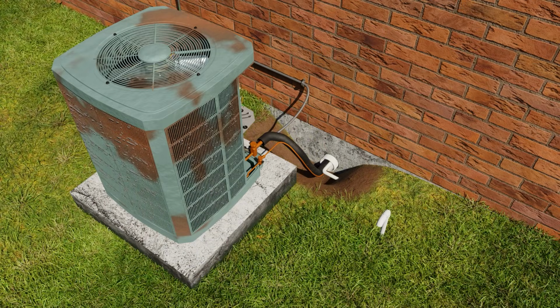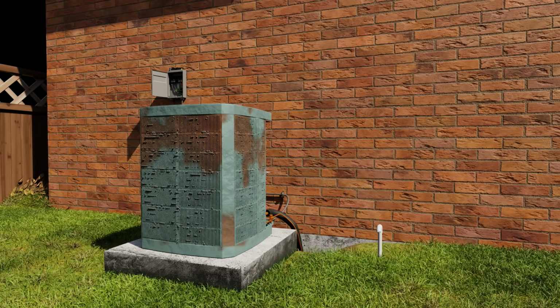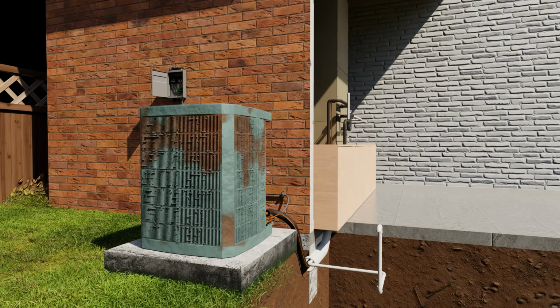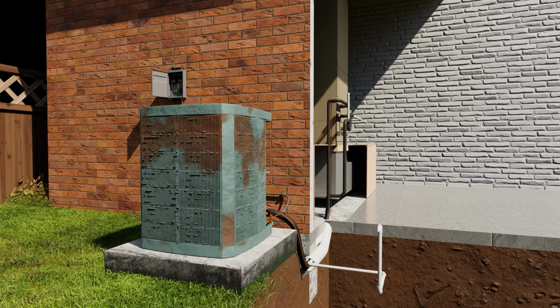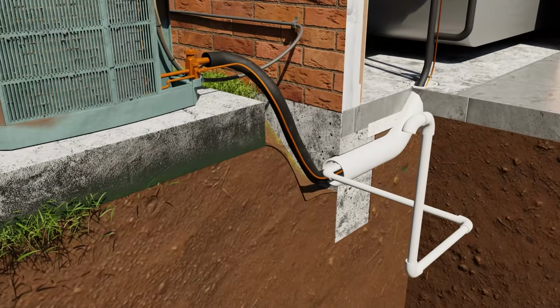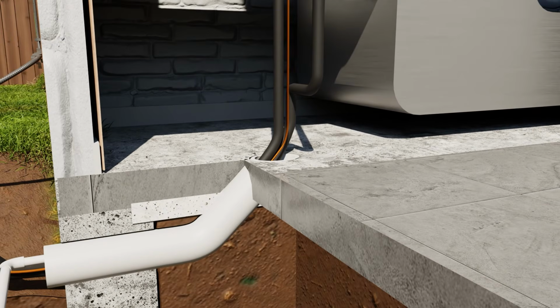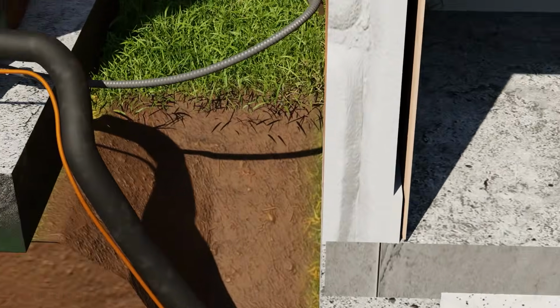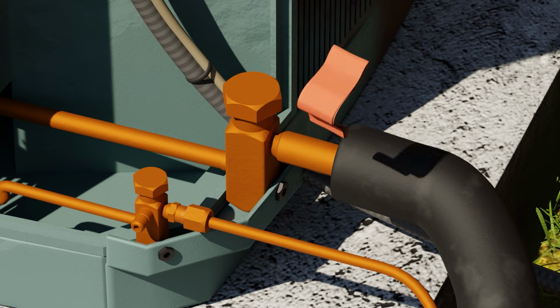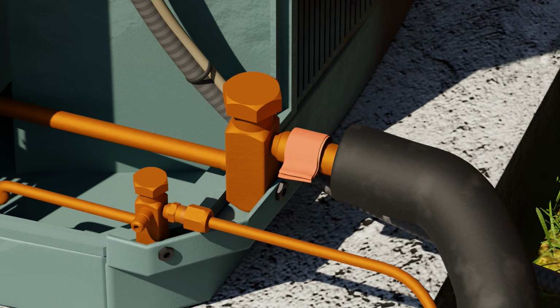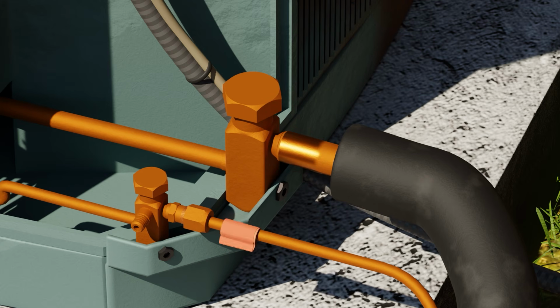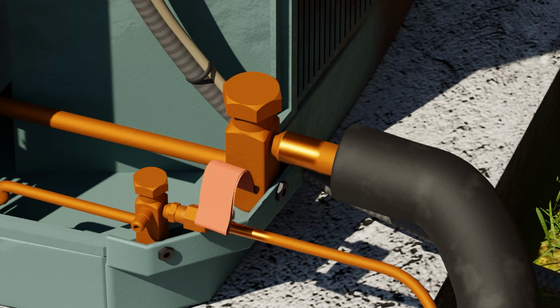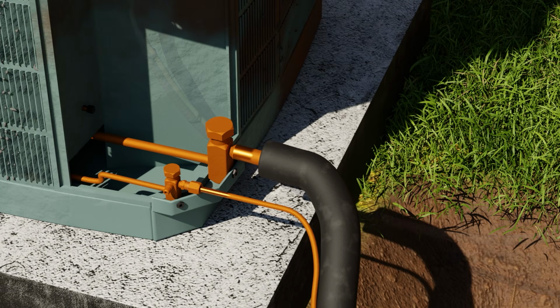At this point, you need to know whether you'll be replacing the copper or reusing it. In the case of reusing it, you'd use a process called pipe wiping to remove any residual oil from the existing copper lines. If you need to replace the copper in an underground application, you need to dig down to the chase and expose it to begin preparing for running new copper. Here we show how a typical chase application would look. The one shown here would be a very short chase application.